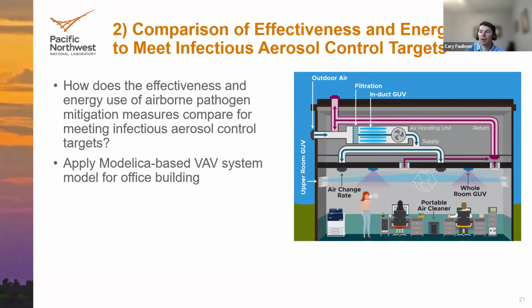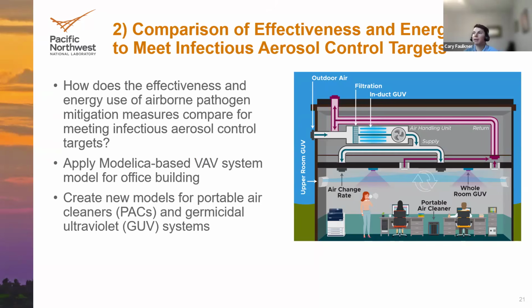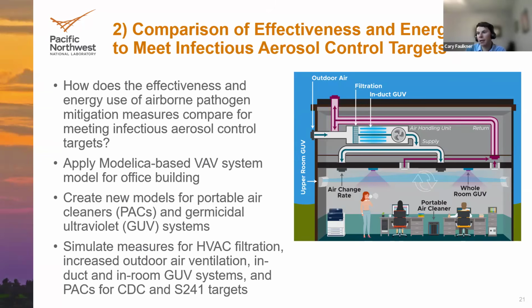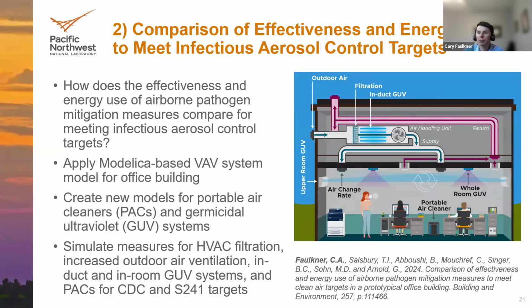we apply the Modelica-based VAV system model once again, but we create some new models to be able to analyze these various airborne pathogen mitigation measures. That includes some of the strategies I mentioned before, like outdoor air ventilation and HVAC filtration, but we also create new models for portable air cleaners to be placed in rooms and filter pathogens, as well as germicidal ultraviolet systems, both in the duct and in rooms, which irradiate in the duct or zones and inactivate the pathogens through that irradiation. And then we simulate those various measures to meet infectious aerosol control targets defined by CDC and standard 241. Similarly, I'll cover some of the model development from this work and results, but there's more to be read about this in this paper in Building and Environment.